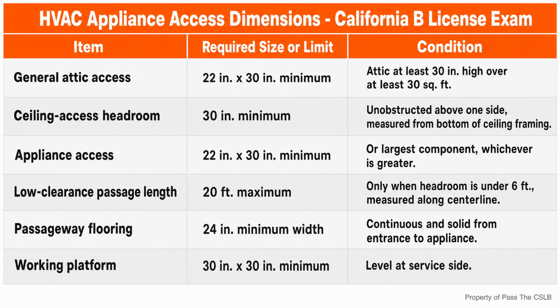After the opening, look at the route. When the attic or underfloor passageway has less than 6 feet of headroom, the distance from the access opening to the appliance cannot exceed 20 feet. That distance is measured along the center line of the passageway. This is commonly overgeneralized. The rule does not say every attic appliance must always be within 20 feet of the hatch. The 20-foot limit is tied to a low-clearance passageway. When the headroom condition changes, do not automatically carry that same limit into a different situation. I would check the actual geometry and the applicable code, not rely on a half-remembered shortcut.